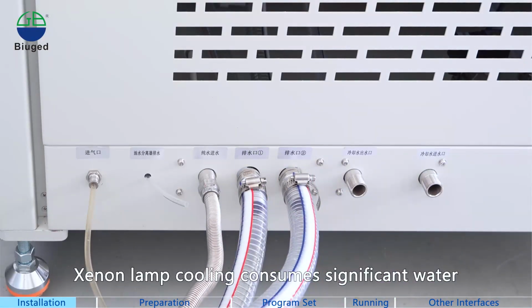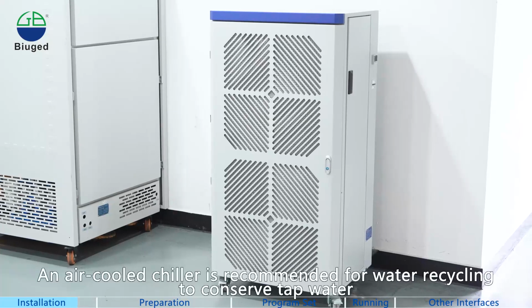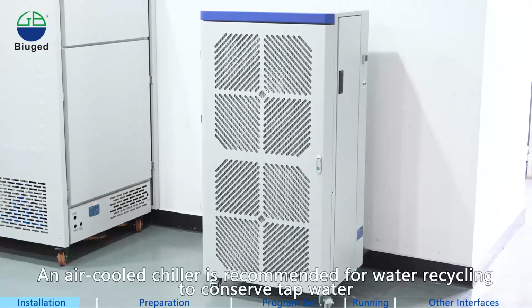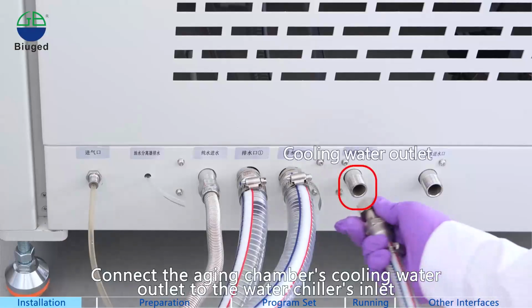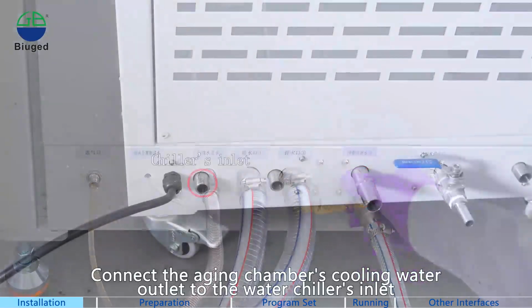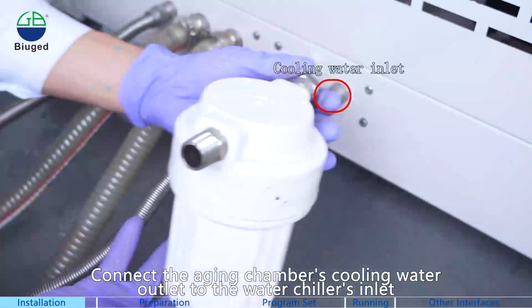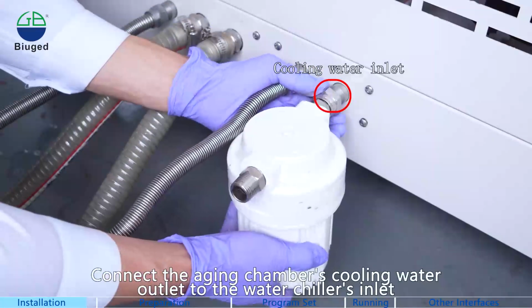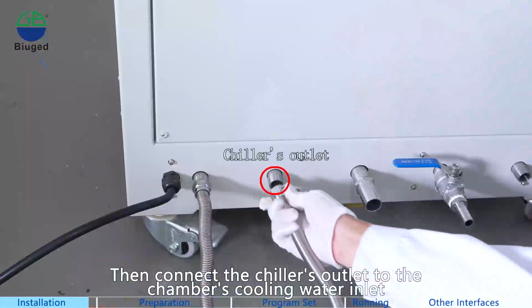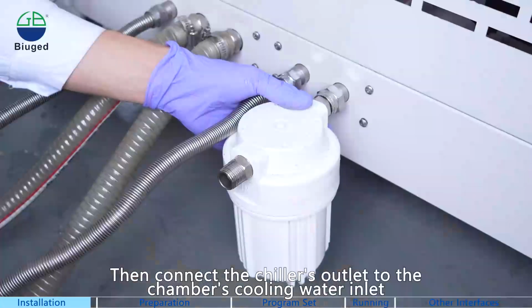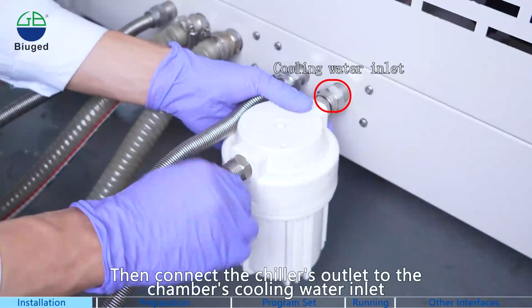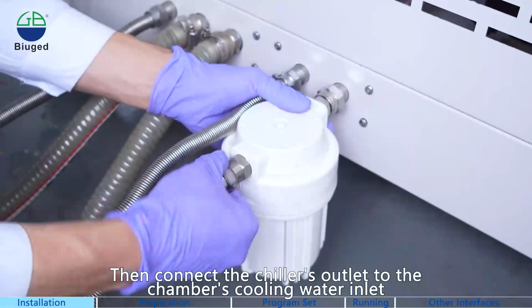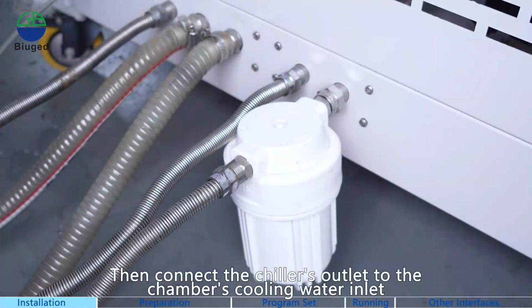Xenon lamp cooling consumes significant water. An air-cooled chiller is recommended for water recycling to conserve tap water. Connect the aging chamber's cooling water outlet to the water chiller's inlet. Note: first install the filter to the chamber's cooling water inlet. Then connect the chiller's outlet to the chamber's cooling water inlet. Note: initial connection of the water purifier must be guided by our personnel.